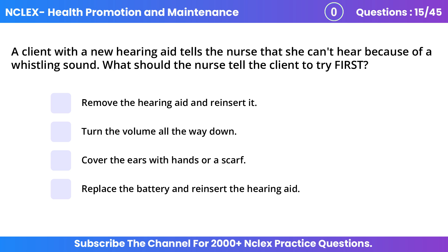A. Remove the hearing aid and reinsert it. The whistling noise is called feedback. Feedback is caused by sounds leaving the ear canal that are picked up by the hearing aid's microphone and then re-amplified. To reduce feedback, the first step is to remove the hearing aid and reinsert it to ensure a good fit. Lowering the volume can also reduce feedback, but try reinserting the hearing aid first.